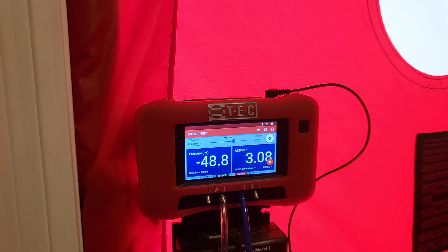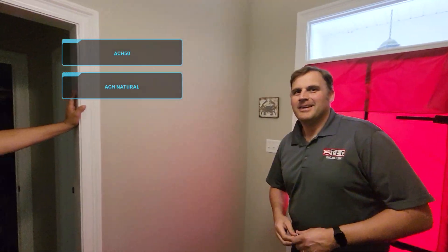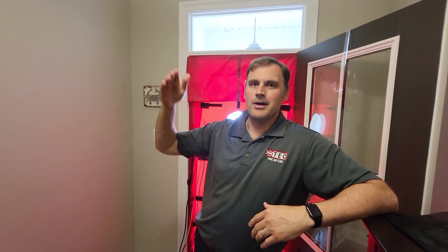There we go — we passed. What's the difference between ACH50 and ACH natural? ACH50 is a test pressure — we're putting a pressure against the house compared to outside, roughly equivalent to around 20 miles per hour wind. It's a good benchmark. ACH natural is what's happening to the house under normal conditions. With a multi-point test, you test at pressures like 10, 25, 35, 45, up to 75 pascals to accurately interpolate a measurement — you don't want to extrapolate. You start at baseline zero, work up to 75, and interpolate back to natural infiltration from the 50-pascal test pressure.